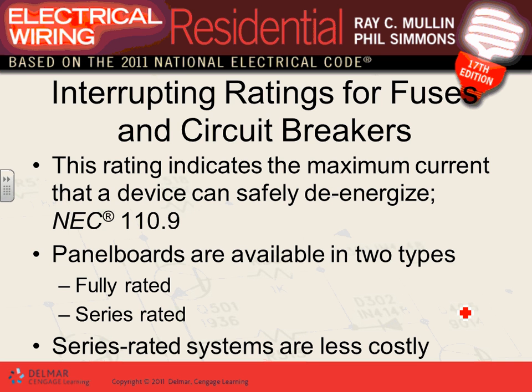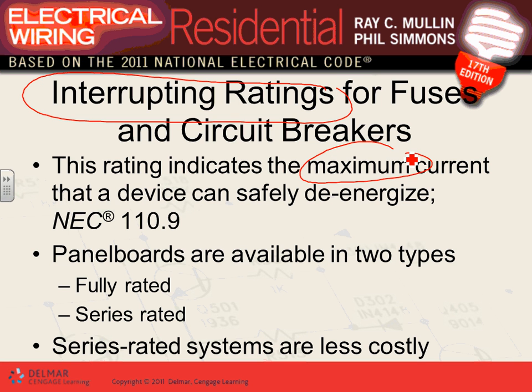Interrupting rating is the highest amount — the maximum current — that the device can safely interrupt in an energized circuit. If the short circuit is higher than what the circuit breaker is rated for, the circuit breaker will explode. You want a circuit breaker that safely interrupts the system so you can reset it and move on.